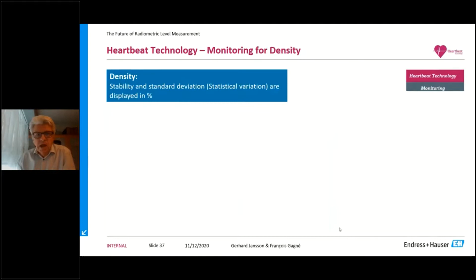If we then talk about density, density is slightly different. First of all, we need to understand that the detector can be either a sodium iodide crystal or this polyvinyl toluene plastic material. The sodium iodide crystal is more stable than a PVT detector is, so that will have an influence on the accuracy. But we also need to understand that radiation is something that will decay over time, but it will not constantly decay. So it will actually fluctuate quite a bit.